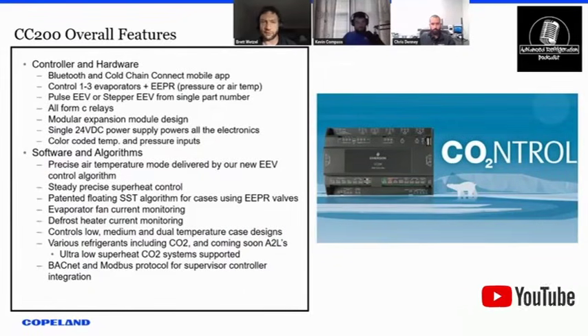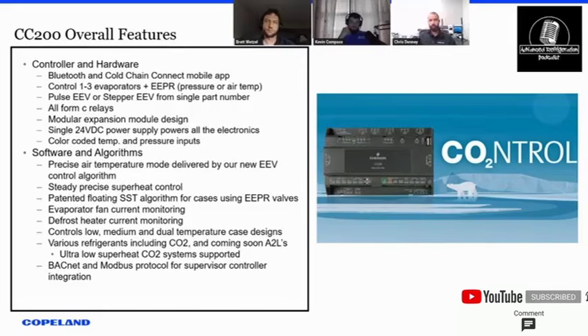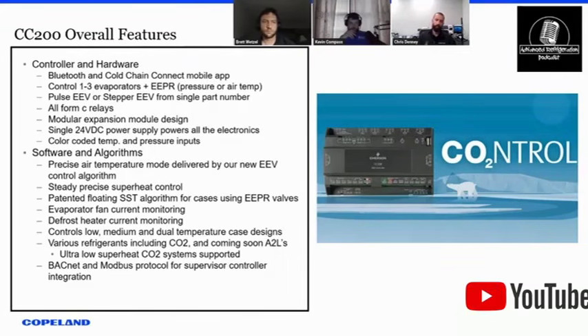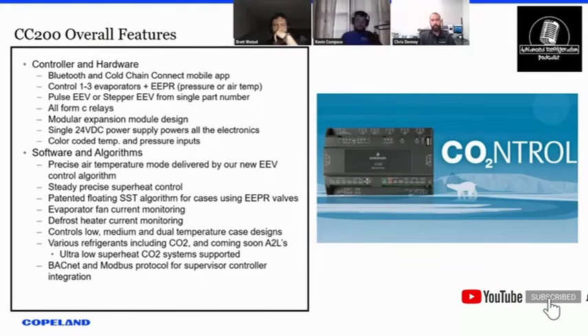So you said you're making one for A2Ls. Does that mean it's going to be a little bit different than that one because of the flammability and that? Yeah, it'll be the same exact controller, but we will swap out some components on the board to get through the UL approvals. So we already have approved components. We just have to basically rework the relays and release an updated rev of the hardware to get that UL approval. And then it'll be a software update to do the mitigation and gas sensor tasks that are required for UL 2-89. So a little bit of software and some hardware swap on the relays for A2L compliance.